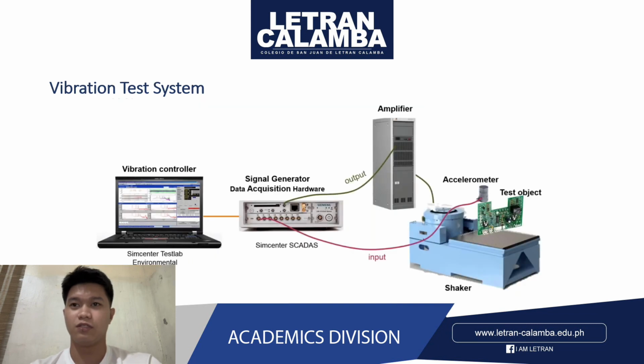So how do we do this vibration control testing? We'll talk about equipment and give a brief introduction to different test types. Here, what we have is a typical vibration control system. The typical vibration control system consists of different elements. First, we have the vibration controller. This is used to manage the test and determine the output needed to recreate the desired vibration levels.